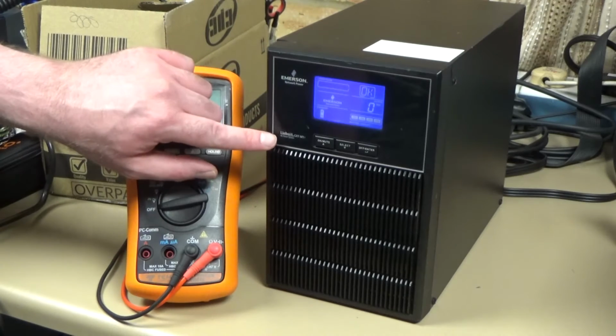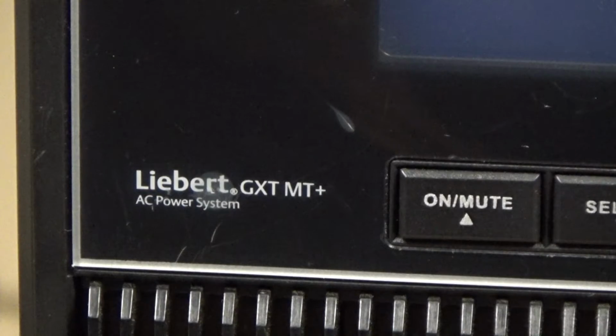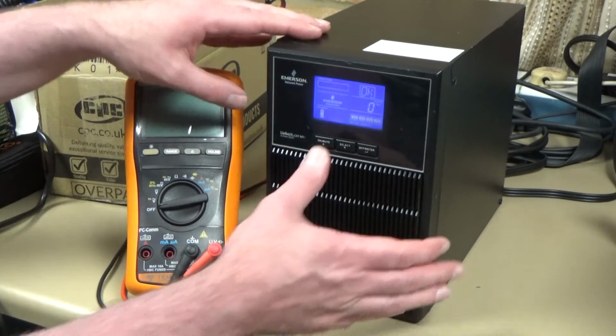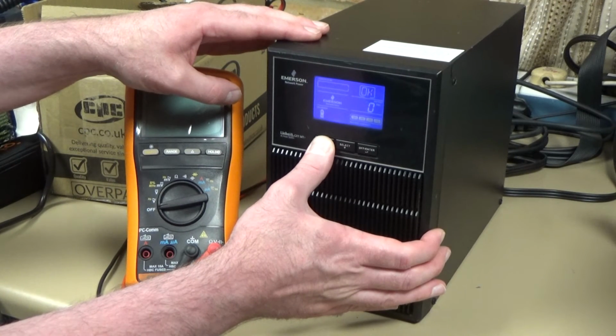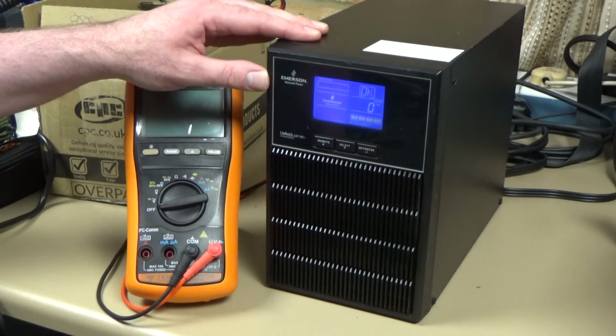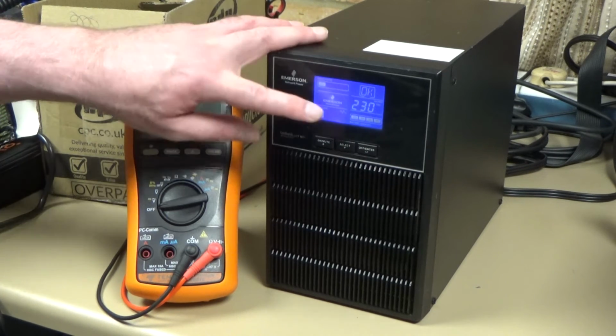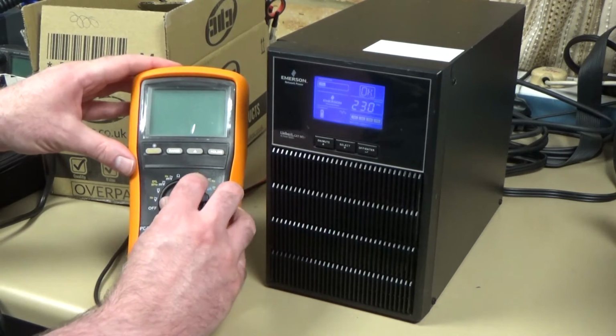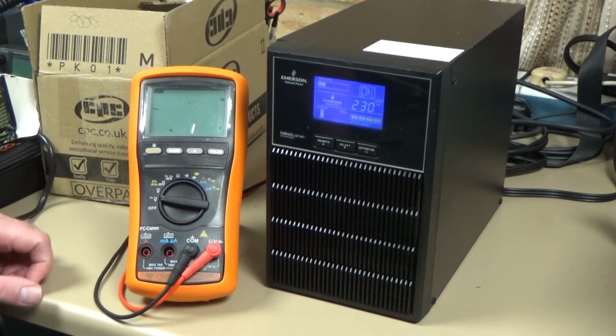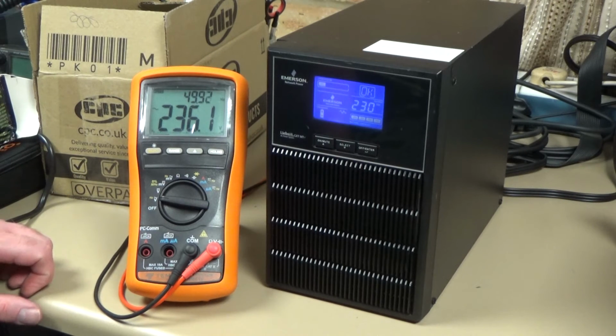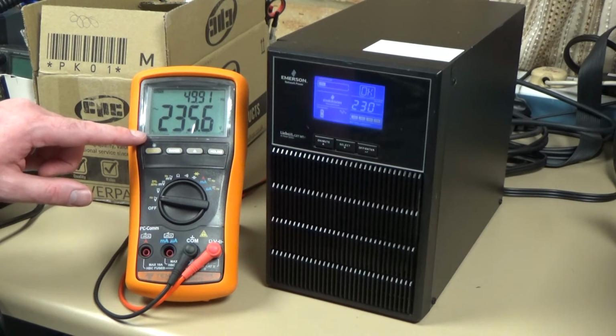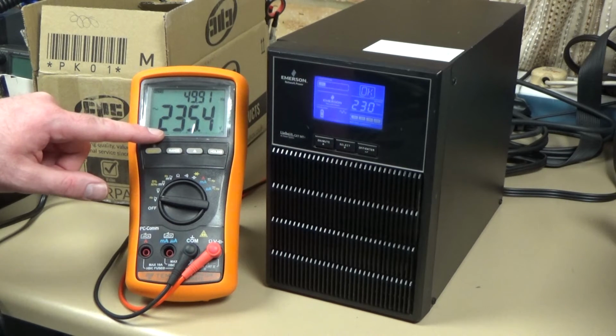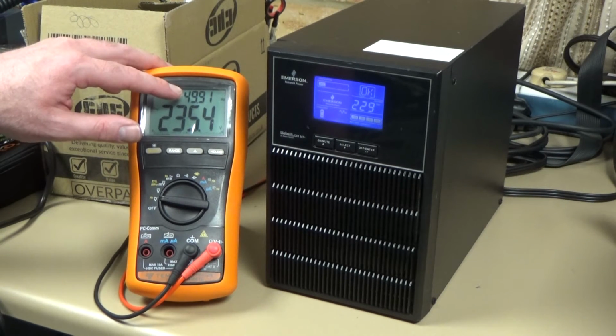It's an Emerson Liebert GXT-MT Plus UPS unit, and if we turn it on, you can see by default it's configured to output 230 volts, and if we turn on the multimeter, which is just hooked up to the output at the back, it's giving us a little bit more than 230 volts, about 235.5 volts, but it's within spec at 50 Hertz.